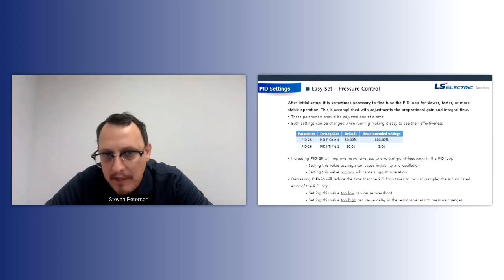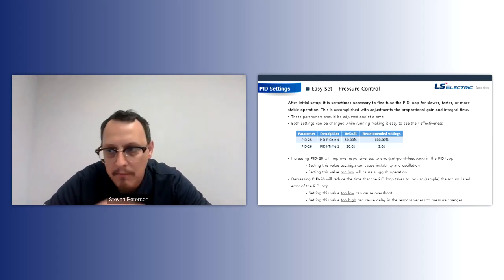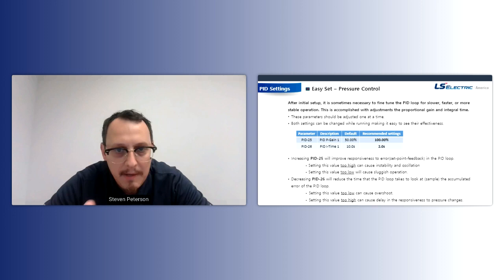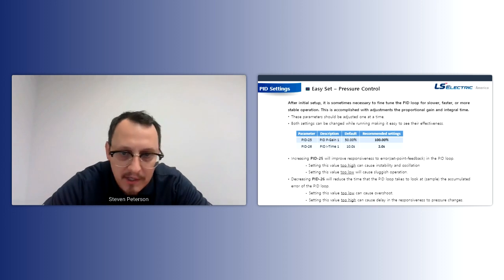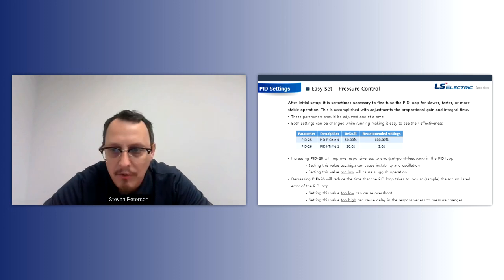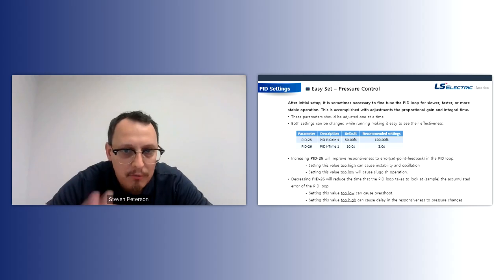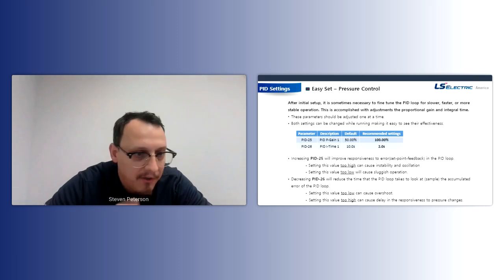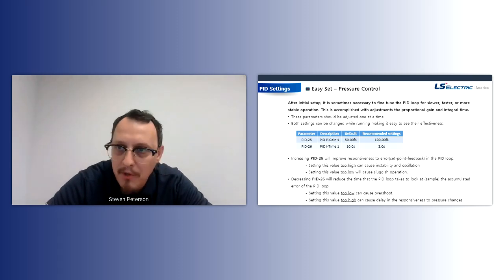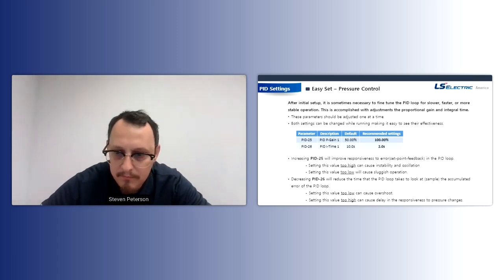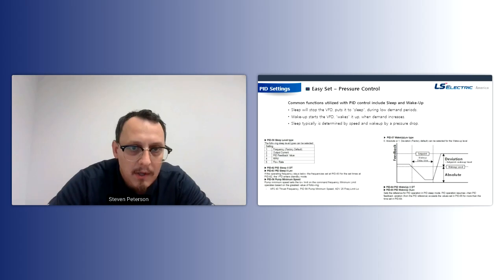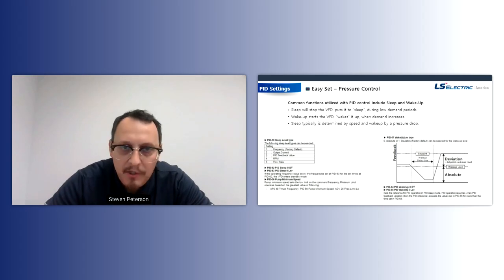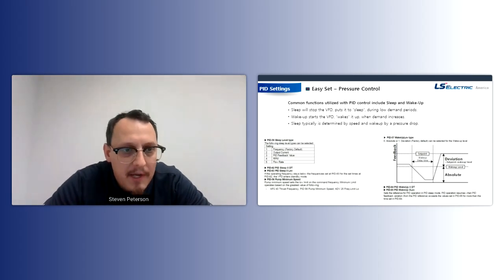Yeah, some critical applications may be running like 400% gain and maybe a 0.1 or a 0.2 second I time. That's pretty extreme, but most pumping applications will be running like 200% gain and maybe a couple seconds on the I time, and most people are happy with that. That is enough to get basic control going for PID.